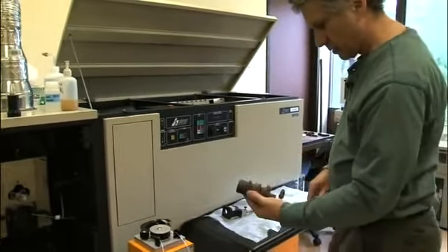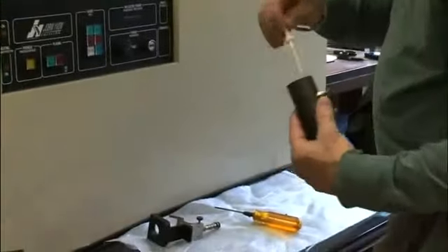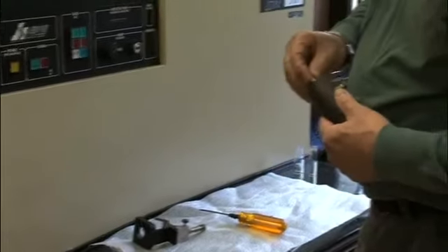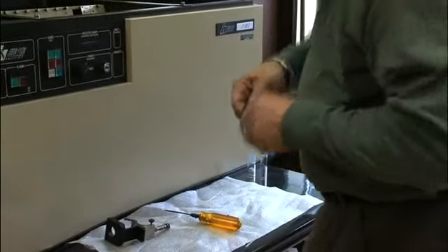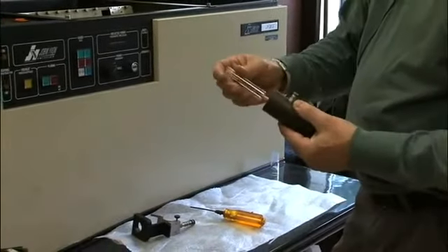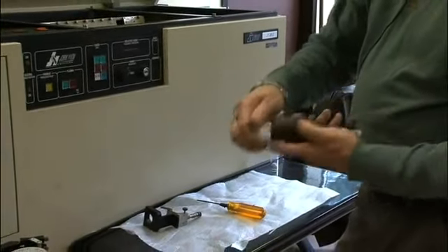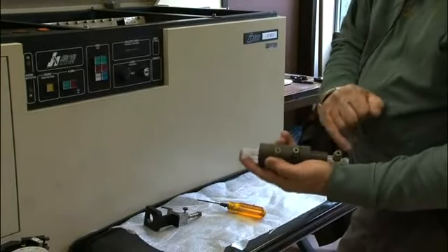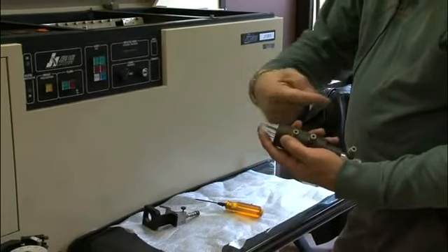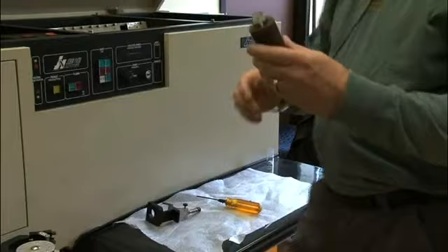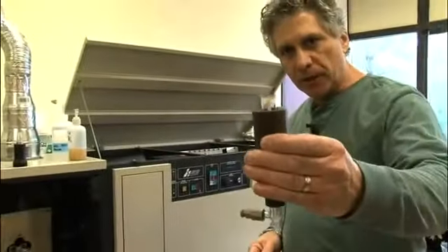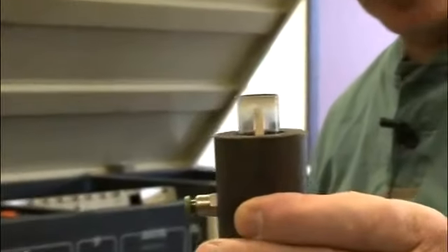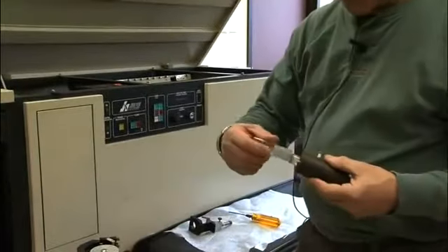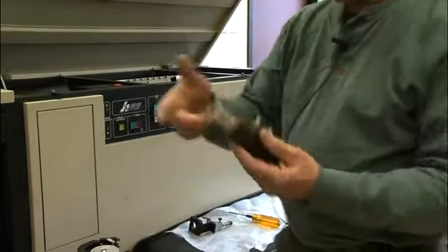It basically just goes like that. This will fit in first. Inner quartz. Now if your Teflon insert down here is seated all the way in and the injector is all the way in, then your injector should be just a hair below the inner quartz tube, which it is. The outer quartz does not go in all the way, so you'll still have a little bit of the frosted area sticking up.